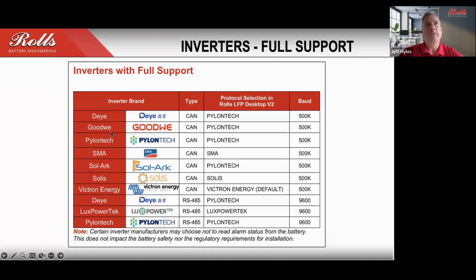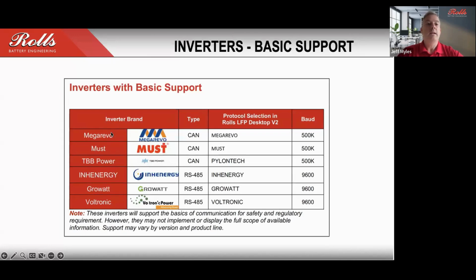So in the case of full support, these units would also report any of those alarm indications. So in the case where the battery has an alarm triggered and it's a condition, say over temperature, for example, it's going to relay that information through closed loop communication to the inverter, and these particular units will actually share that information. It may be on screen, it could be through other notification, but it's essentially going to be shared through the inverter. In the case of basic support, the communication is still there. However, in some cases, the alarm conditions may or may not be shared, and that depends on the particular models and so on. But we've broken it out to set that expectation.